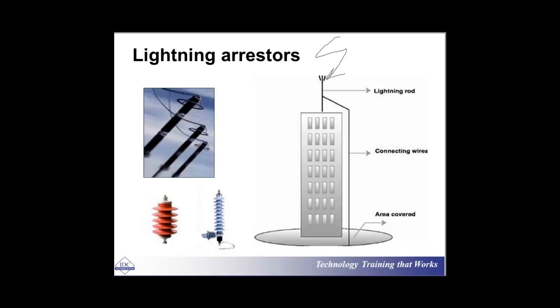So it will conduct hundreds of thousands of amps, which is as a result of the lightning, to the pavement. But that pavement is not going to kill someone, because underneath the pavement you have got a very, very complicated and comprehensive earthing system. So that massive short circuit current, under good design, should be dissipated away into the matrix and earthing network that you have previously established underneath the ground at an appropriate depth.